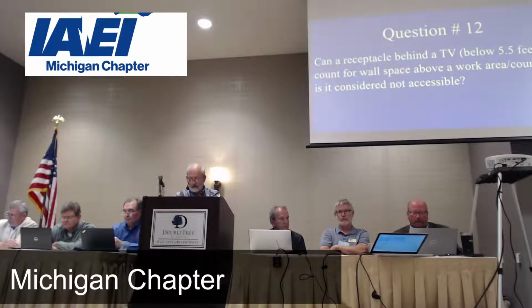210.52 does give us all our spacing requirements. It talks about the floor receptacle within 18 inches, all those kind of things, but it does not call the TV out as an item that would not allow that as accounting for your wall space.